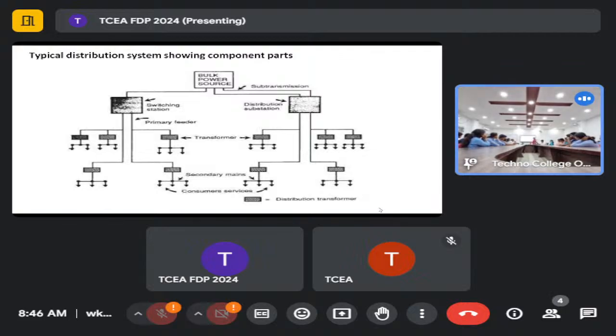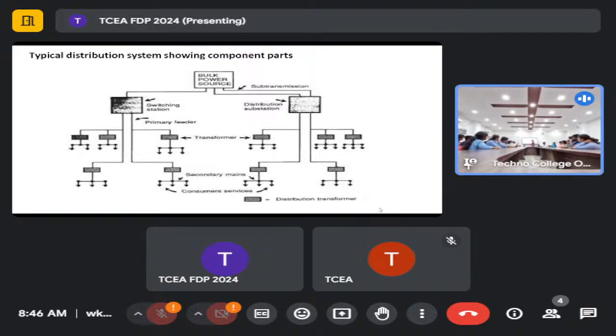Here is a switching station, and here is the primary feeder — this is totally separate from the distribution substation. The switching station is part of the high voltage transmission system, because you cannot ensure proper regulation and proper voltage level over a very distant place without it. If you send power from here to a distant point, a switching station is required. Is that clear to you? Any other questions?